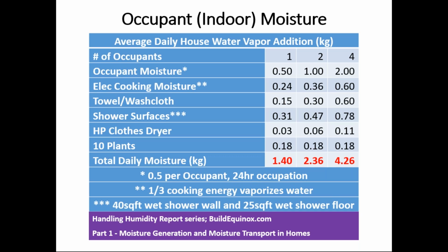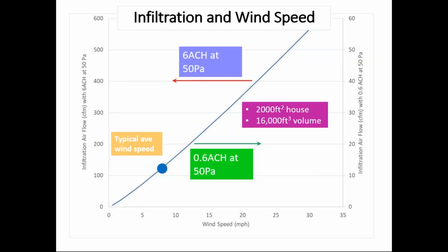But of course, if you're exercising, perhaps there's more because you do breathe more, your metabolism increases, and you perhaps are perspiring, which can be an additional significant load. But all of these add up to somewhere in the range of maybe a kilogram, a liter, to 1.5 liters per person per day. There's some scaling as you go to 2 people to 4 people as far as the amount of moisture that might get deposited on shower surfaces and things, as you see here. But somewhere in the range of, say, 1 to 4 liters per day for a typical house occupancy of 1, 2, 3, or 4 people.